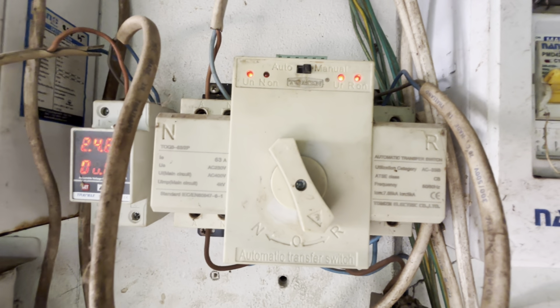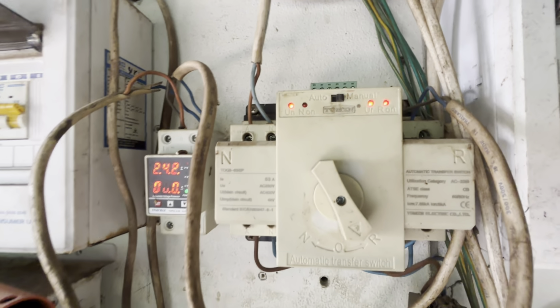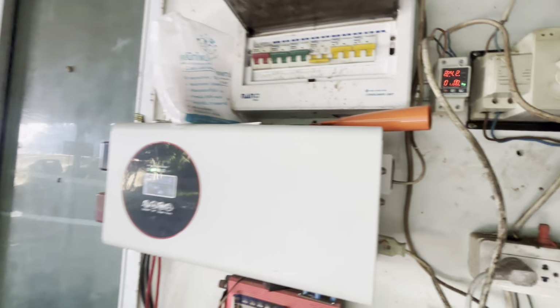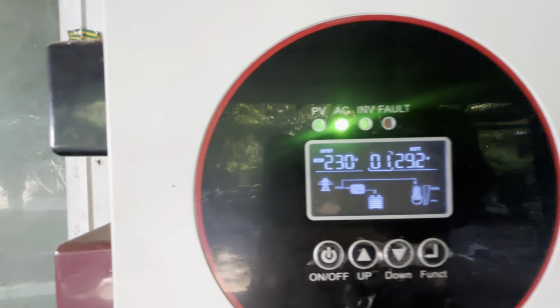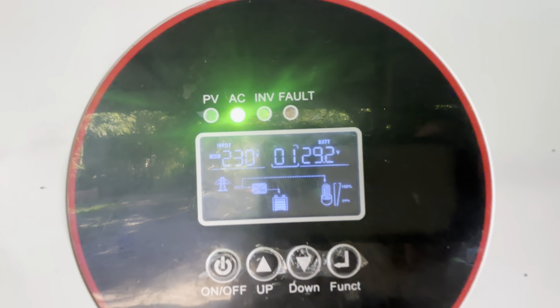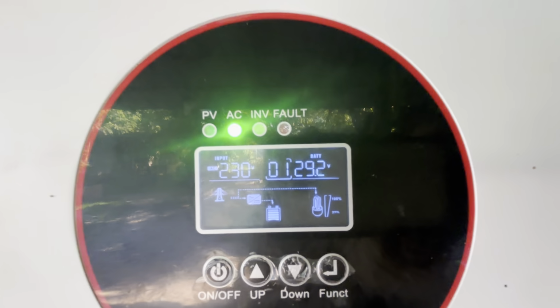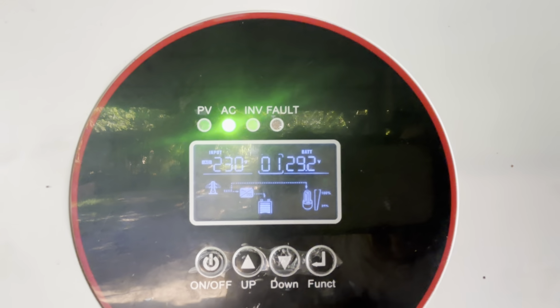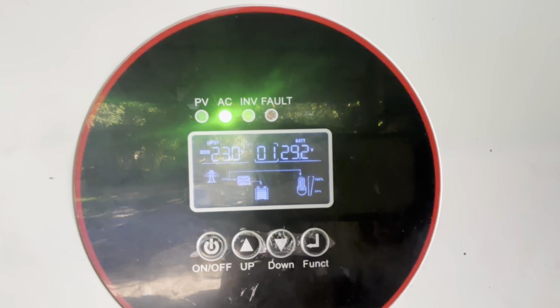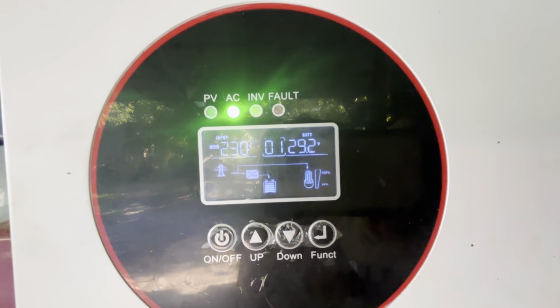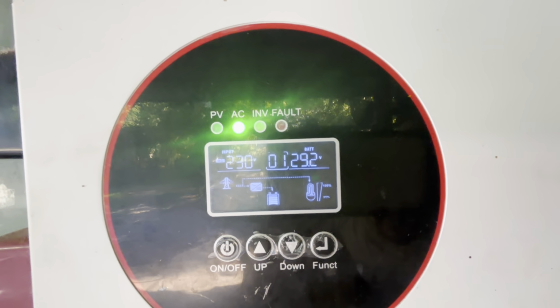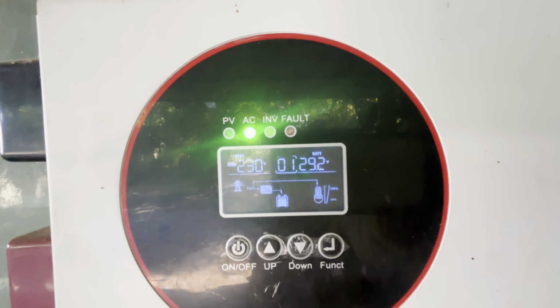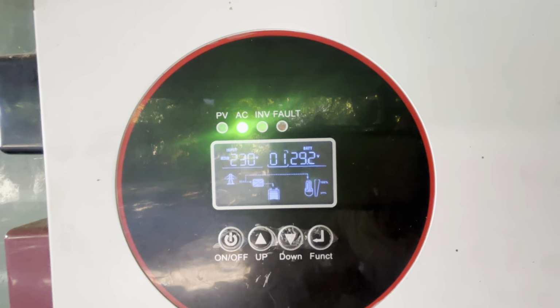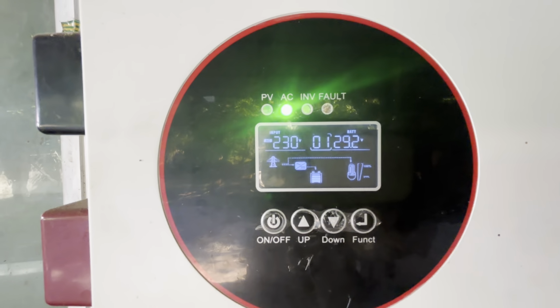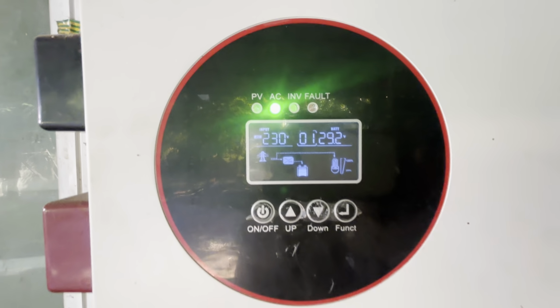Anyway, at the moment you can see what it does. It gives you the incoming voltage, and then the battery voltage. Because it's reading 29.2, you know it's not being used. As soon as the batteries take the load, that will go down. It drops to about 28, and after around 10 minutes it'll sit at 26.2 for ages, then it just drops straight off. It doesn't come down linearly.